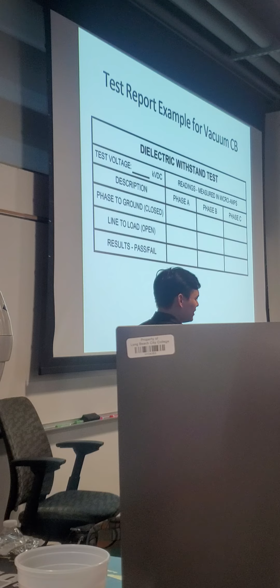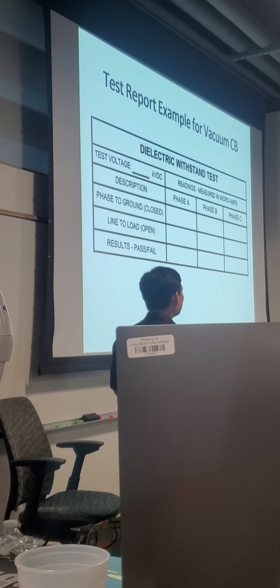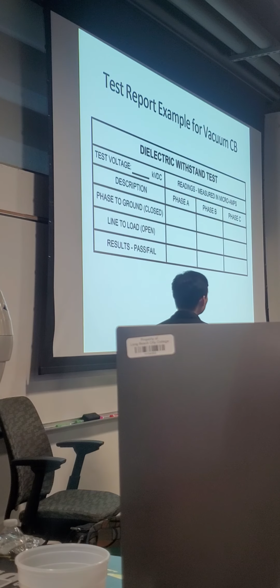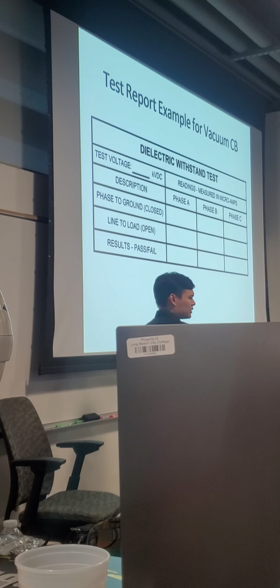In that case, you deliver the test noting A and B phase failed the dielectric withstand test. In some cases, we've had a failed vacuum bottle, and they swapped out that bottle on the spot. We were able to retest, and it actually helped, and after that it passed the vacuum test.